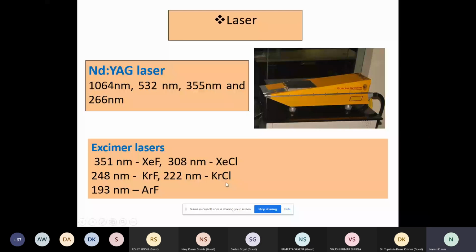However, in the case of a solid-state laser, there is no such issue of consumables. Yes, after a few million shots, maybe the flash lamp needs to be replaced, but that's not very expensive. I would say you can get a flash lamp for about $500. So that's one important thing I wish to share.